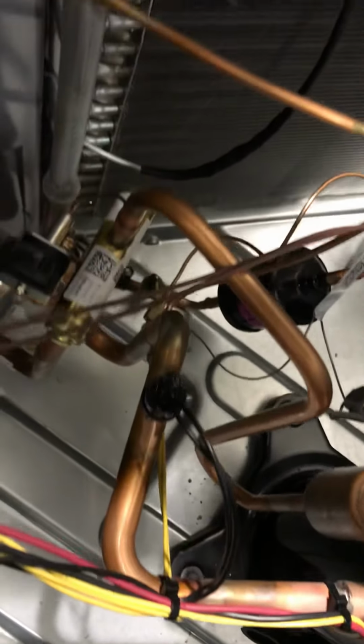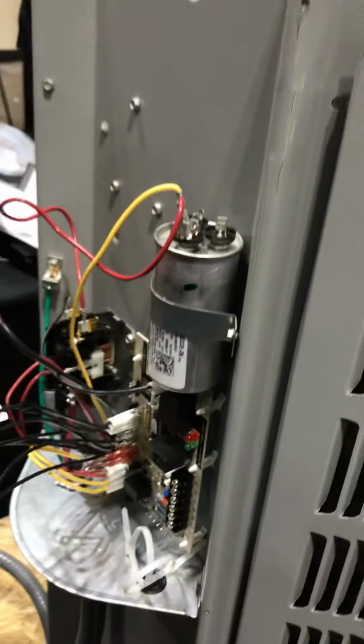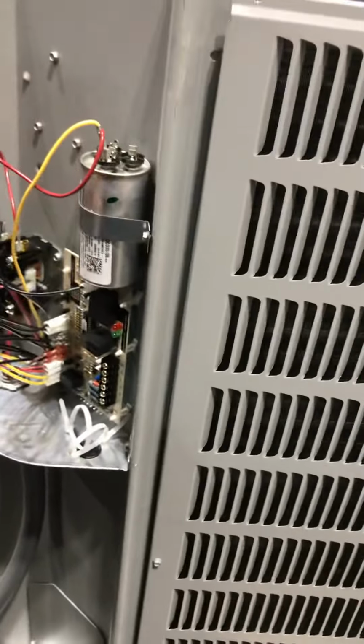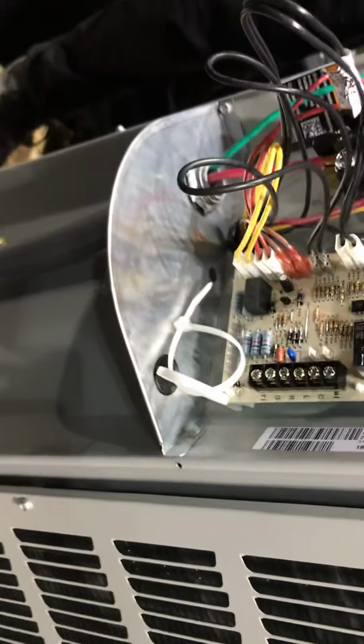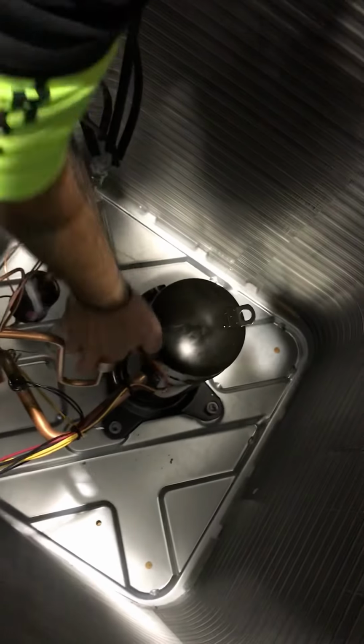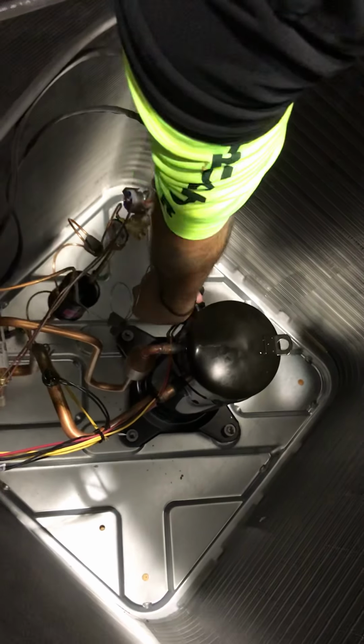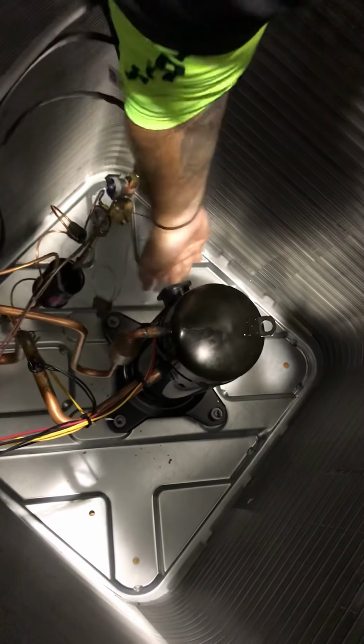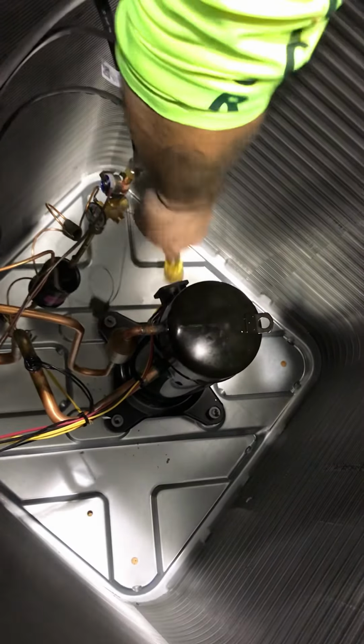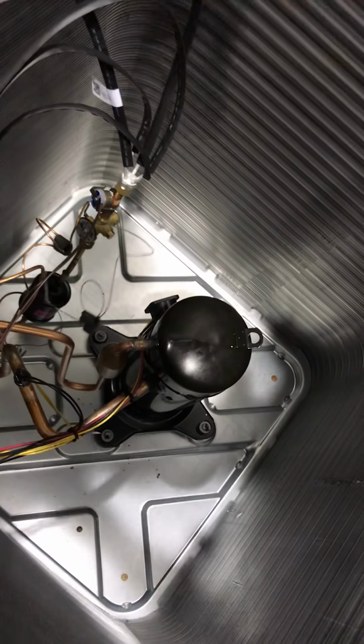High pressure is usually a thinner copper. Yeah, high pressure is going to be thinner. It's also considered liquid. High pressure will always be considered with liquid. Low pressure, your suction, will always be considered with vapor. And that's all the electrical components in here, other than my junction plug for my compressor, which is here. Goes in right there. That's bringing in 120 volts. So that's what that is.